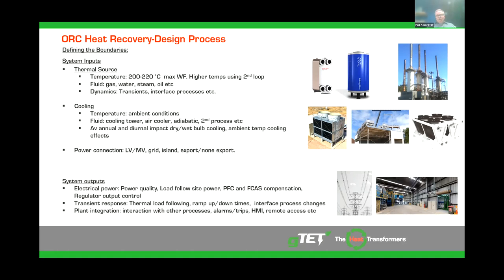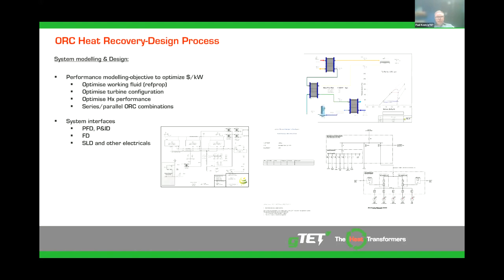Two, transient responses such as thermal load following, ramp up, ramp down times, interface process variations into the generator. And three, plant integration, including interaction with other processes, alarms, trips, HMI, and remote access. So with the boundary conditions defined, the system can be modelled. Our computer models have been refined to optimise the working fluid selection, optimal turbine configuration, optimised heat exchanger performance, series parallel ORC combinations, with the objective being to optimise the generator's Capex dollars per kilowatt output. I guess that's our major metric, is the dollars per kilowatt.